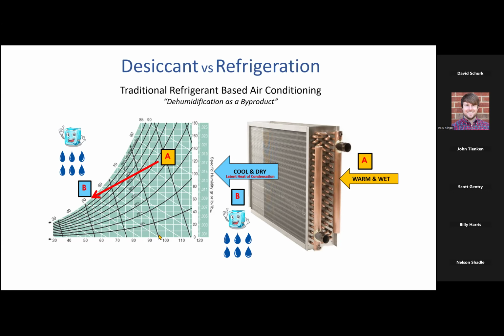And we can see sensibly I'm taking that air from maybe 100 degrees Fahrenheit and 130 grains per pound down to about 55 degrees Fahrenheit, 55 degree wet bulb, 55 degree dew point, and maybe 63 grains per pound, something like that. So I have cooled the air sensibly. I have reduced the amount of moisture in the air. I have hit saturation over here on the psychrometric chart, and I have condensate forming. And I'm removing moisture based on the temperature of the air leaving the coil.